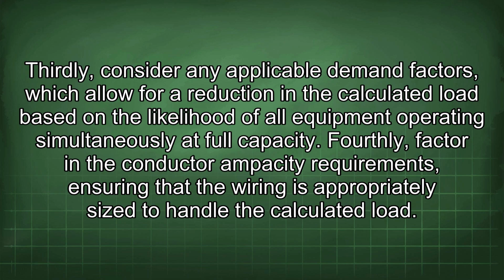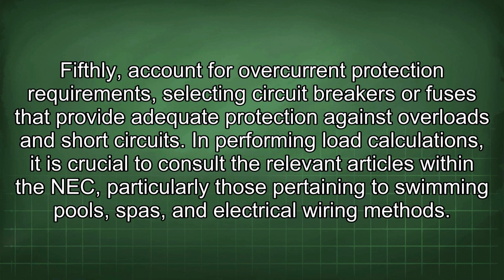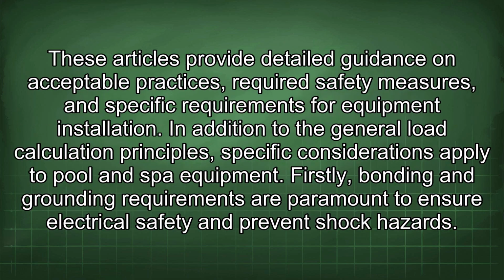Fourthly, factor in the conductor ampacity requirements, ensuring that the wiring is appropriately sized to handle the calculated load. Fifthly, account for overcurrent protection requirements, selecting circuit breakers or fuses that provide adequate protection against overloads and short circuits. In performing load calculations, it is crucial to consult the relevant articles within the NEC, particularly those pertaining to swimming pools, spas, and electrical wiring methods. These articles provide detailed guidance on acceptable practices, required safety measures, and specific requirements for equipment installation.